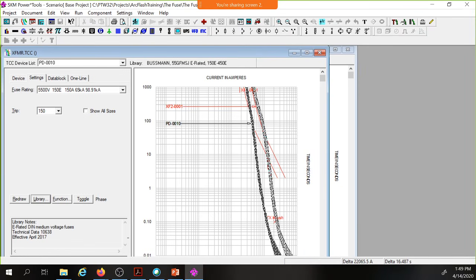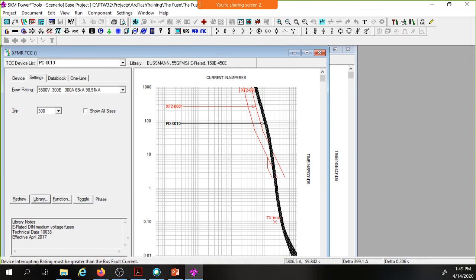All right, and somebody had mentioned earlier about providing too much of this, so let's talk about that. This portion of the damage curve: think about the fuse on the primary of the transformer. It's there for short circuit protection of that transformer. Your secondary main overcurrent protective device is going to limit the amount of load you put on this transformer. This is a 1500 kVA transformer; divide that by 0.48, divide that by 3, multiply by the square root of 3, and you get 1804. So you're at about 1800.